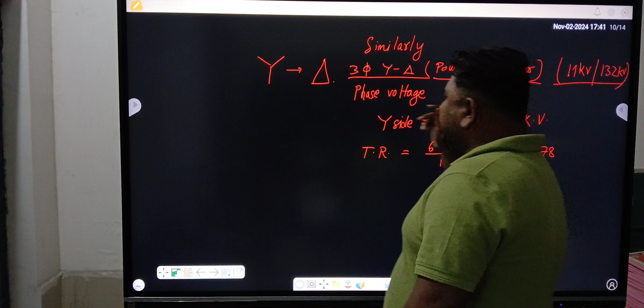There the higher voltage was 11, it was divided. Here the higher voltage is, as for the rating, suppose the rating will be 11 kV by 132. Okay. So what will be the higher voltage over here? 132. So again you can divide 6.351, which is the phase voltage on star side, by 132. That is the higher voltage. You will be getting a ratio.